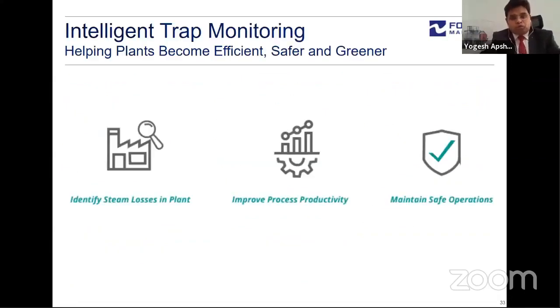Second is the intelligent trap monitoring. What is the need of a trap monitoring system? Because a trap is looked at as a commodity, meaning no one is caring for the steam traps. But the steam trap is a very important aspect of a steam system, because it is the only equipment which understands the difference between the steam and the condensate. Otherwise, there is no equipment in the steam system which understands the difference between the steam and the condensate. So steam traps are the barriers between the condensate and the steam.